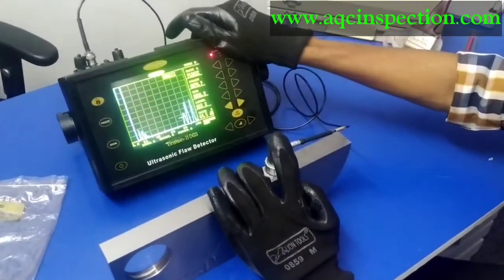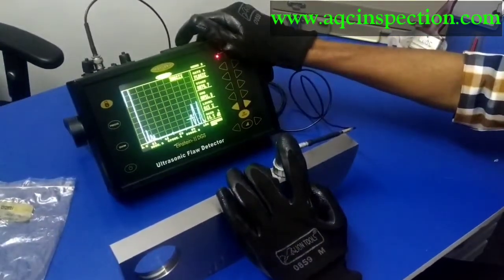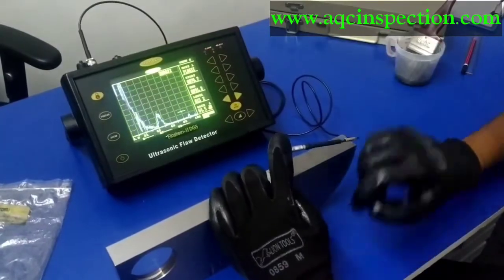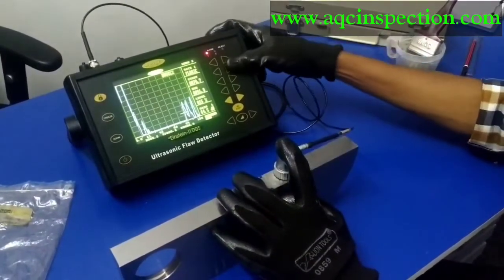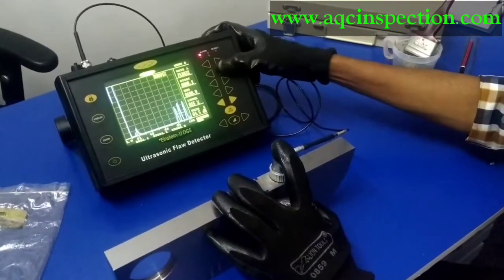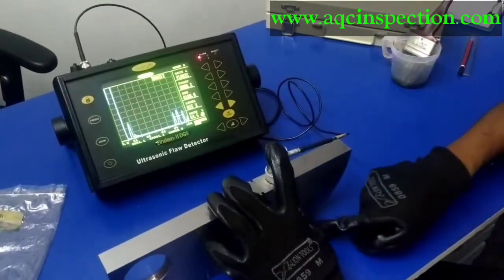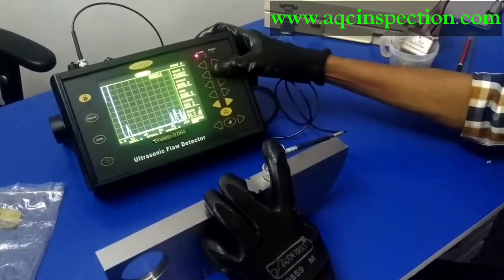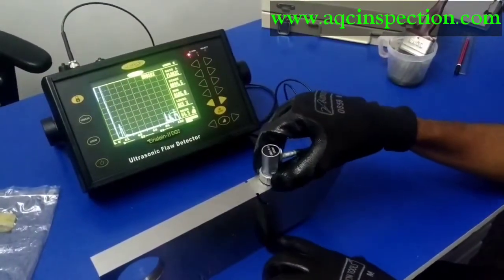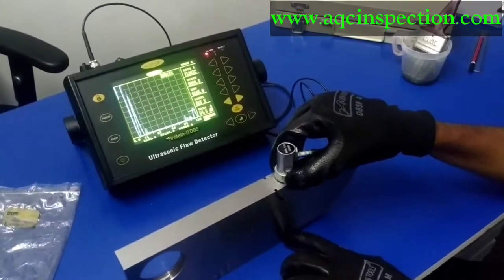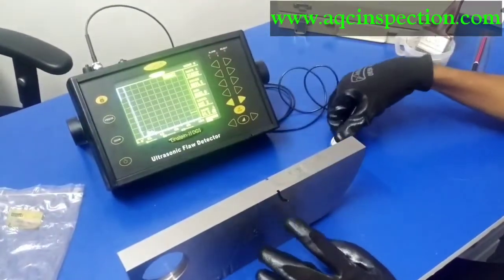So the first backwall, the first echo I am receiving is 85.6 which is right, this one. This is the first echo. And the second one that I am getting is 91 which is this surface right here. And the last one is 100 mm, which is the backwall of this material. This is what we call a resolution check.